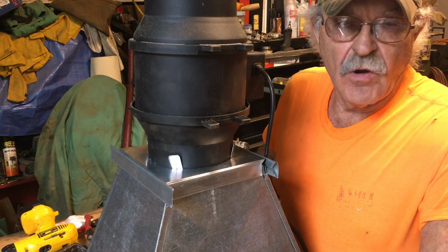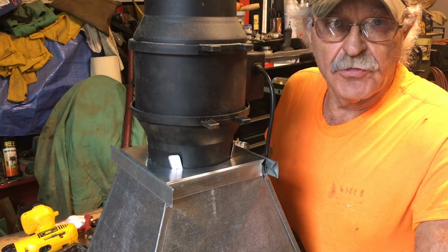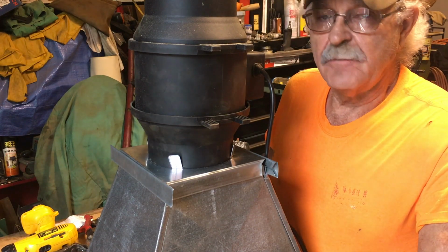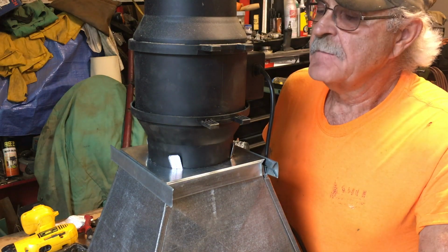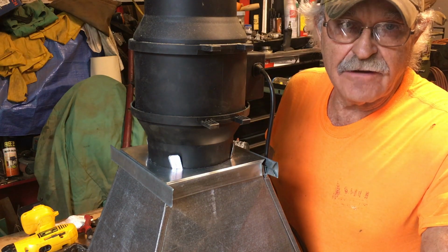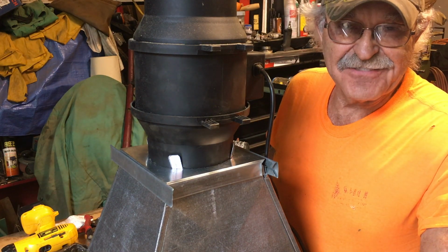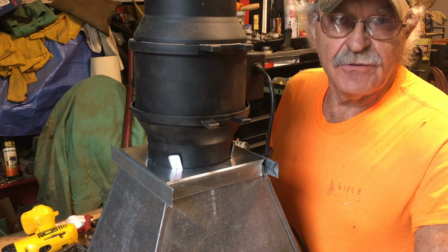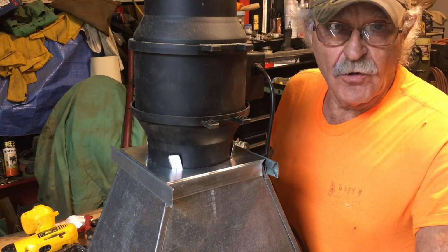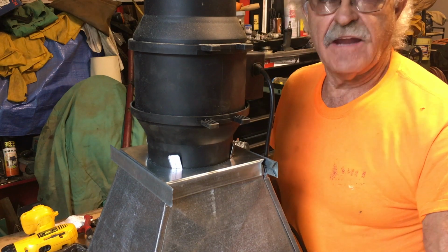He'll be able to balance the water, the gallons per minute going through the coil by means of a valve. We're not going to put a circuit setter on it or anything like that. Then he'll be able to tailor the airflow to what he needs to satisfy the heat load within that basement entertainment area.